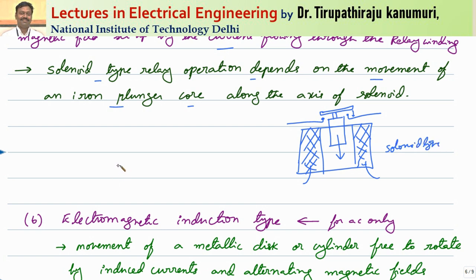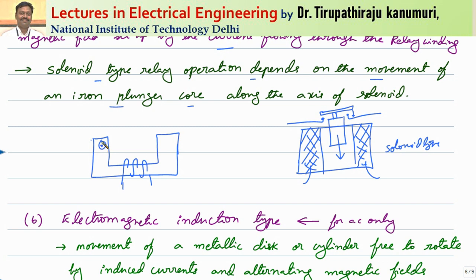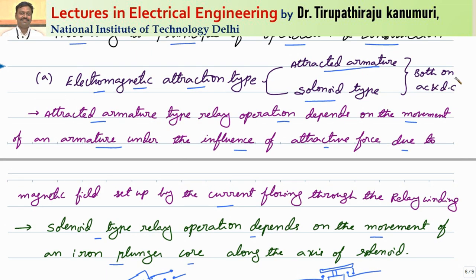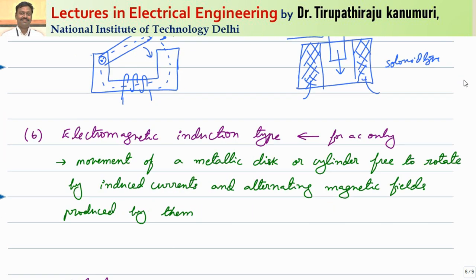Coming to the attracted armature type — there is a coil and an iron bar with contacts attached. Whenever the coil is energized, the magnetic field will attract the iron bar, which moves and closes the two contacts. Because these are based on attractive force, the electromagnetic attraction type can be used both for AC as well as DC.